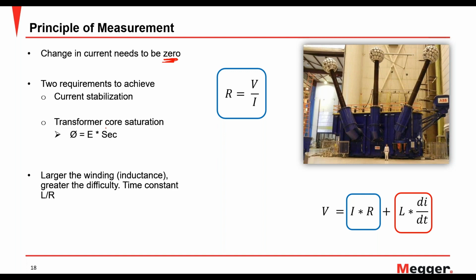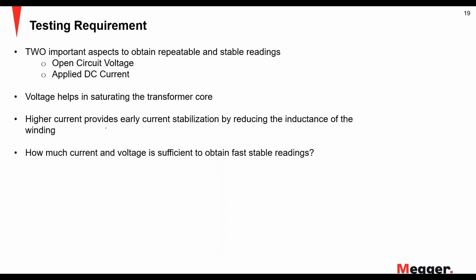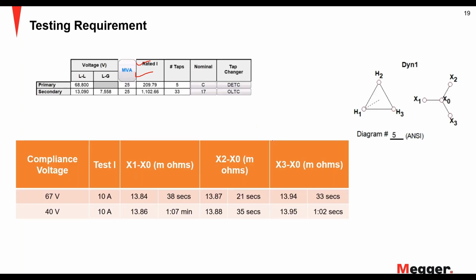So that's when your current and voltage play a big role, because the more current that you supply at a higher voltage, your core saturation will be faster. So that's what it's saying here. Two important aspects: your open circuit voltage or your compliance voltage and applied DC current. Two important aspects to keep in mind while doing a winding resistance test. Voltage helps in saturating the transformer core, and higher current provides early stabilization. So you are not waiting there for 2, 3, 4, 5 minutes for the current to stabilize, and then you get your reading. So how much current and voltage is sufficient to obtain fast and stable readings?